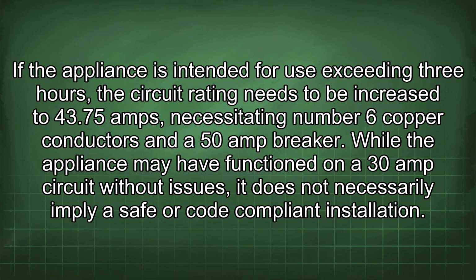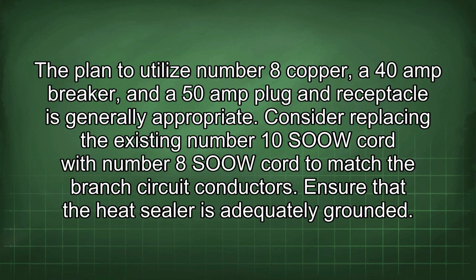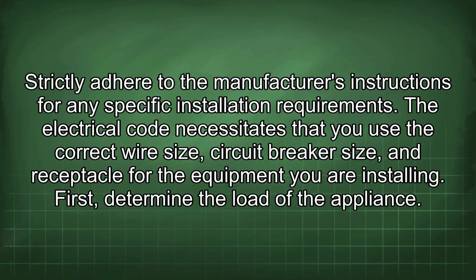While the appliance may have functioned on a 30 amp circuit without issues, it does not necessarily imply a safe or code compliant installation. The plan to utilize number 8 copper, a 40 amp breaker, and a 50 amp plug and receptacle is generally appropriate. Consider replacing the existing number 10 sub cord with number 8 sub cord to match the branch circuit conductors. Ensure that the heat sealer is adequately grounded. Strictly adhere to the manufacturer's instructions for any specific installation requirements.